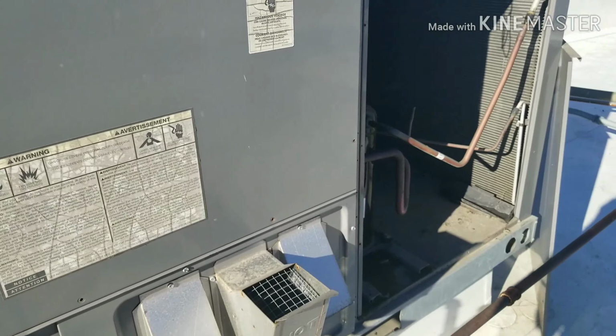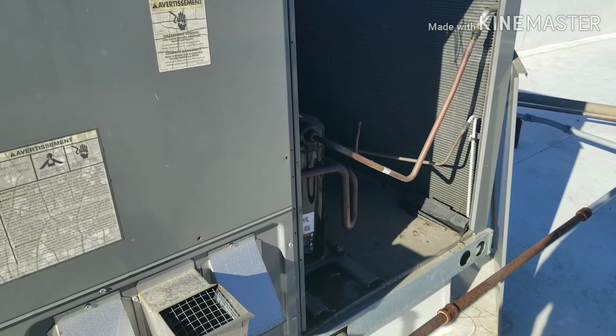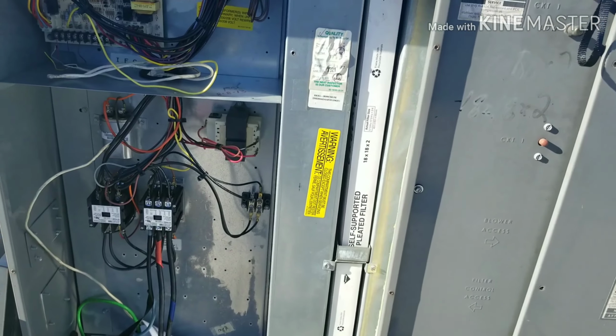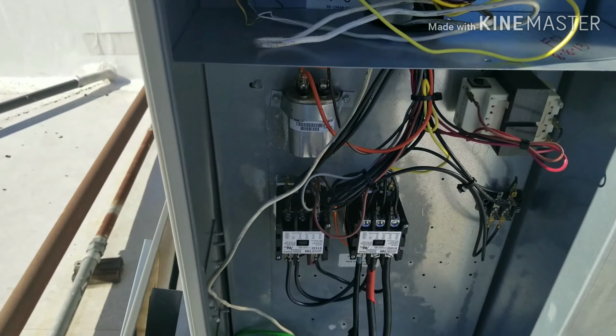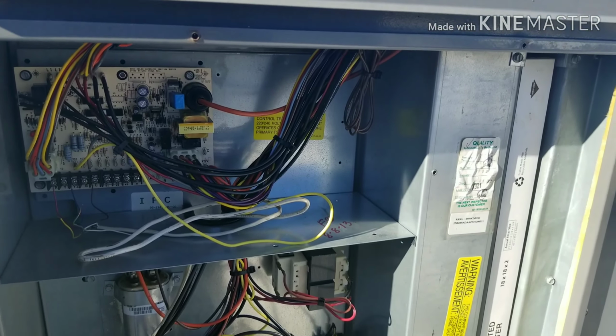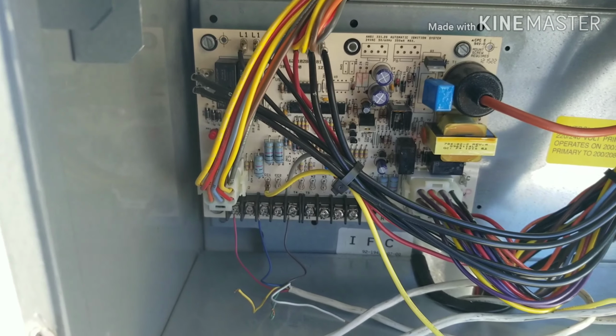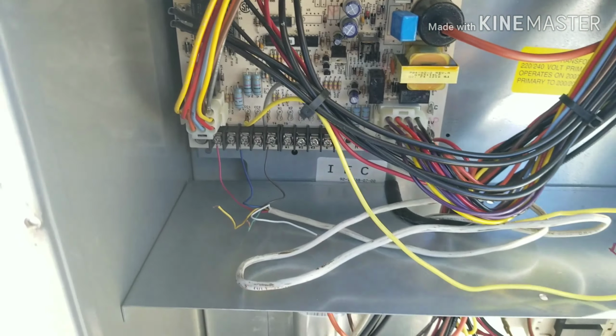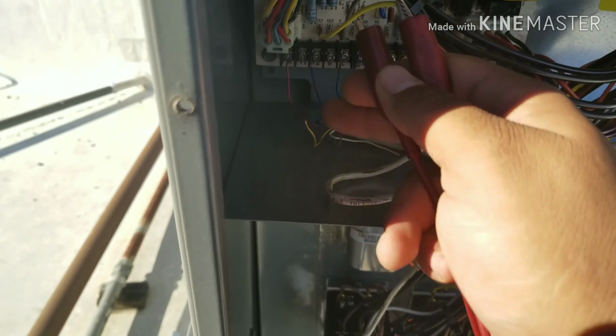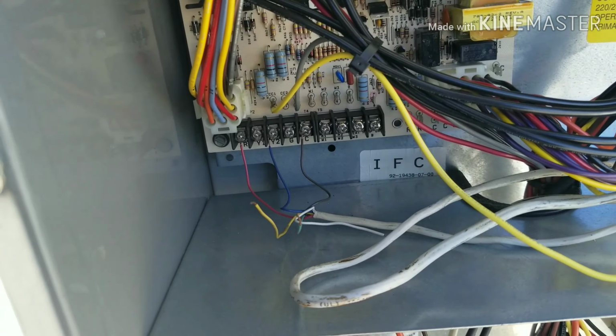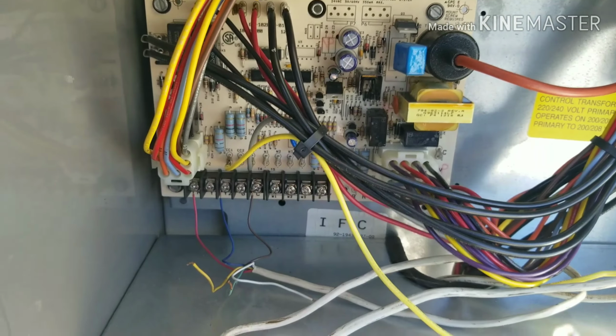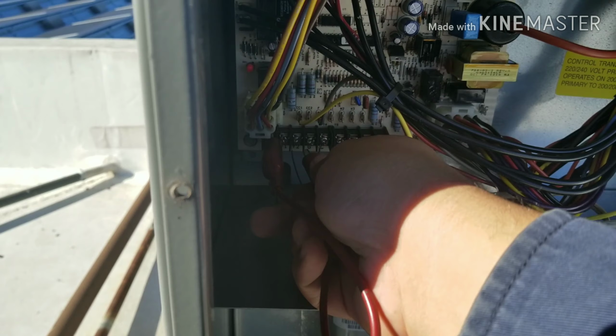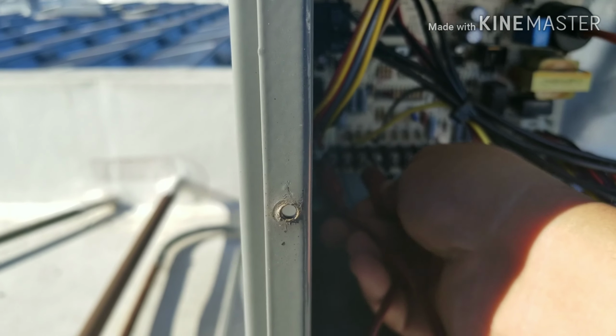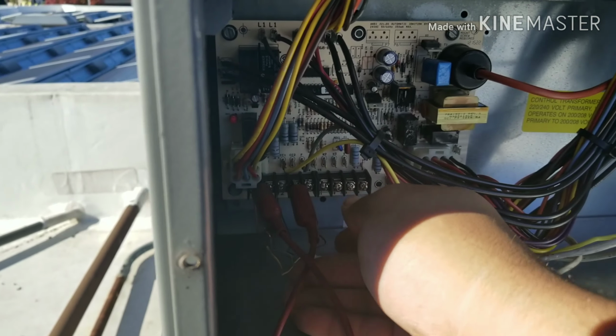At the same time, we're gonna be checking out the thermal image, the infrared image, so you guys see how it looks like. All right. So like I said, I disconnected the wires, so I'm just gonna grab the jumpers. Just be careful because it does have high voltage in here. So what I do is I hit the R, and then we're gonna test the fan first, and there it is.